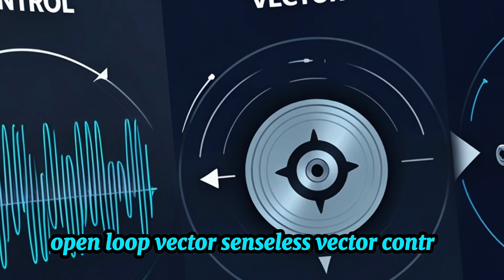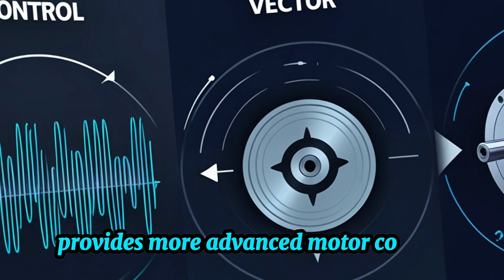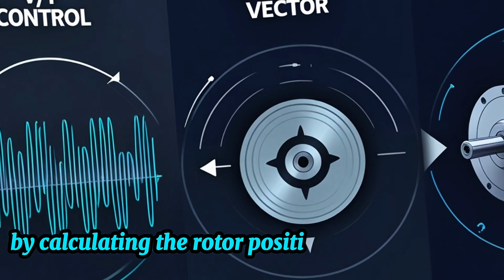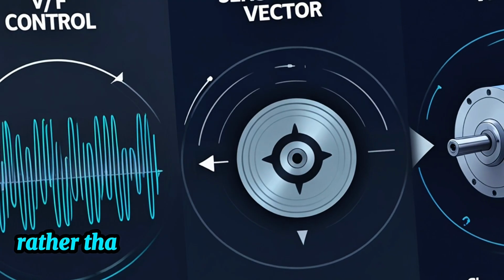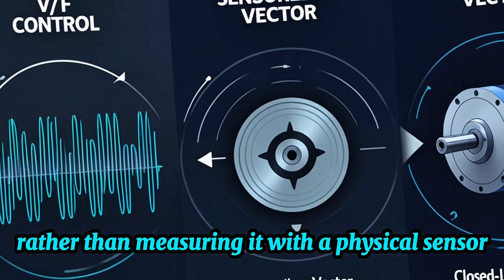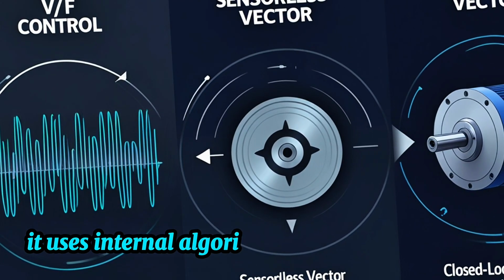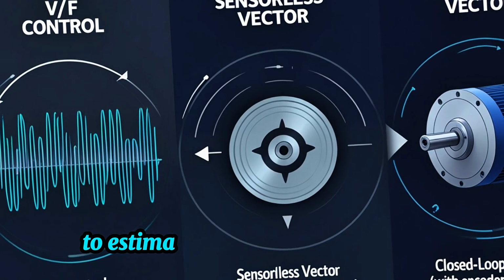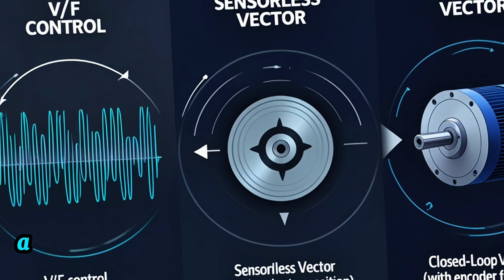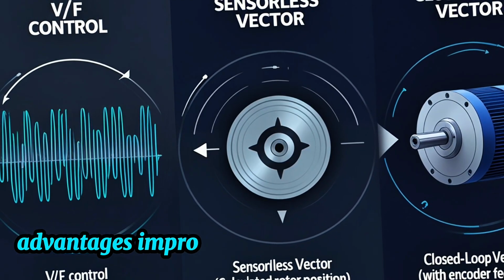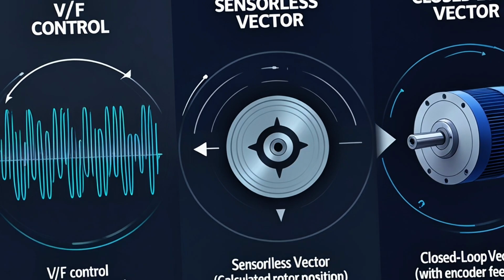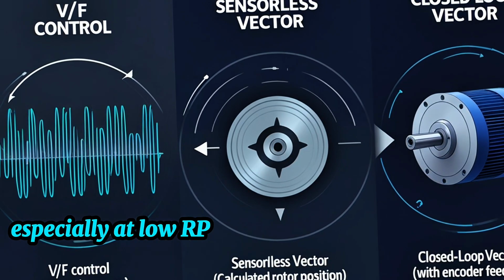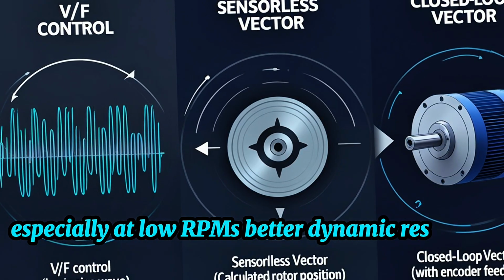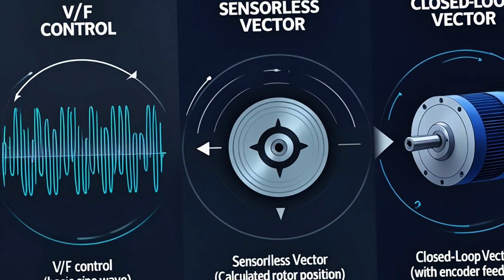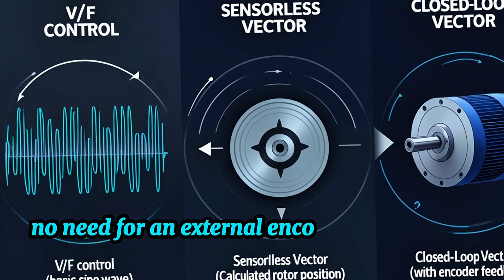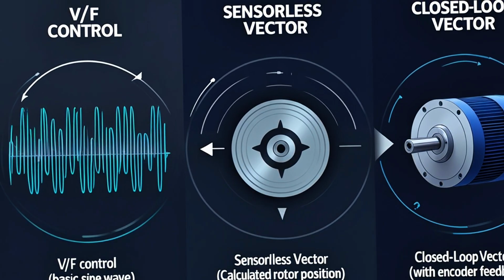Sensorless vector control provides more advanced motor control by calculating the rotor position mathematically, rather than measuring it with a physical sensor. It uses internal algorithms and motor models to estimate real-time performance. Advantages: improved torque and speed control, especially at low RPMs. Better dynamic response to load changes. No need for an external encoder or feedback device.